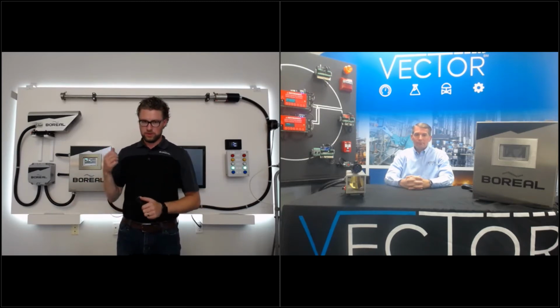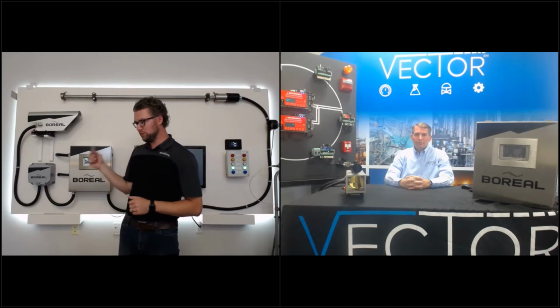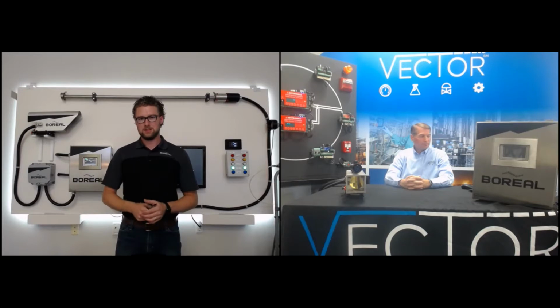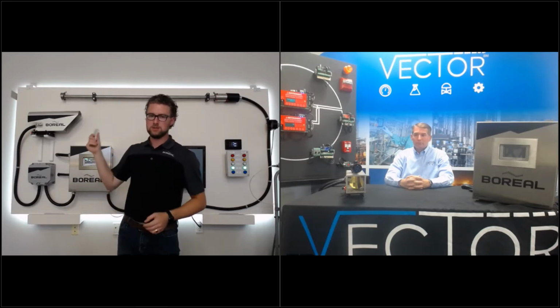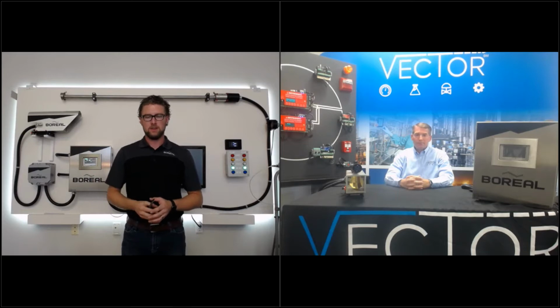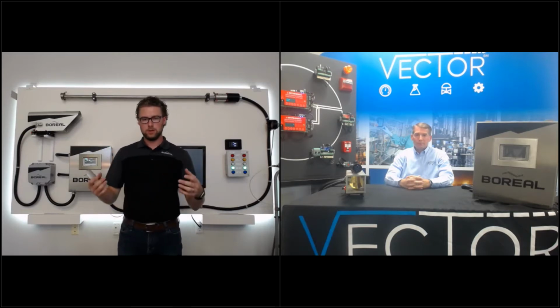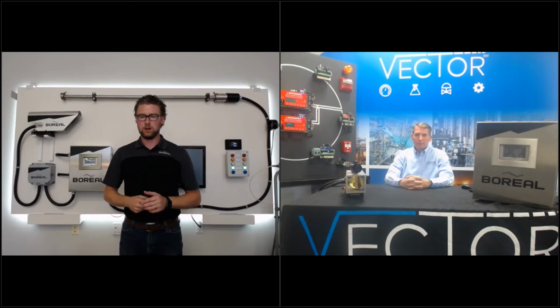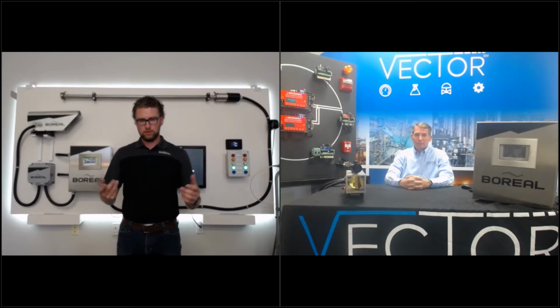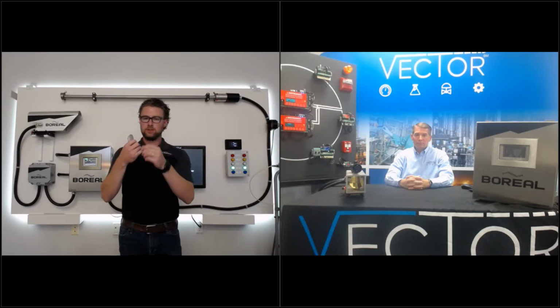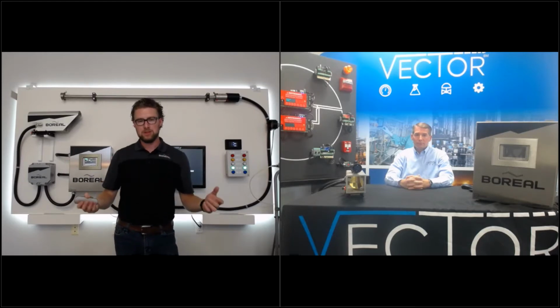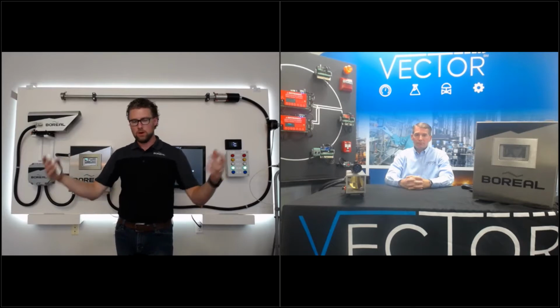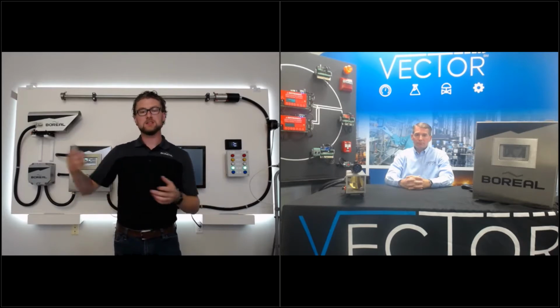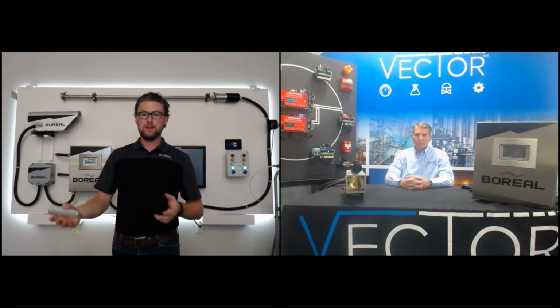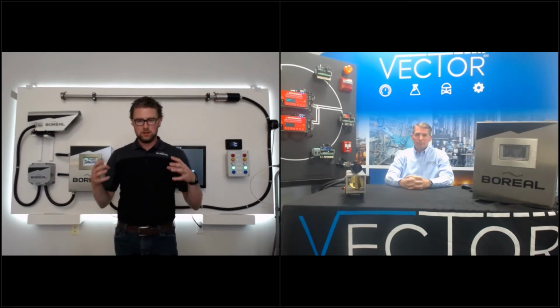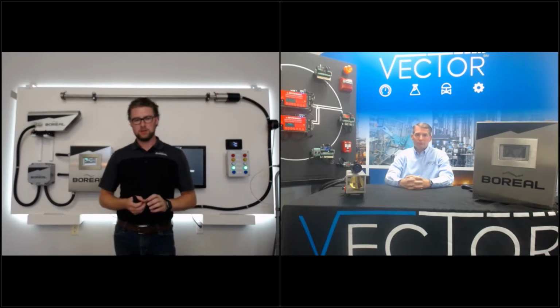But the big thing, what we want to share with you and educate all of you about this enhanced safety system, is that this particular sensing element increases the odds of you detecting the leak because this is an open path or line of sight instrument. The odds of detecting are also increased because of the speed of response that this product and this technology has. Traditional fixed point gas detectors, think of electrochemical sensors, think of cat bead sensors, take on order anywhere from 10 seconds, 30 seconds, and in some cases, all the way up to 3 or 5 minutes, depending on the gas and depending on the weather shrouding at those locations as well.